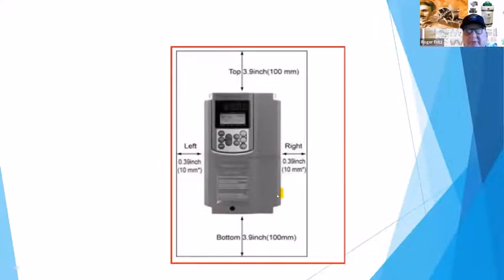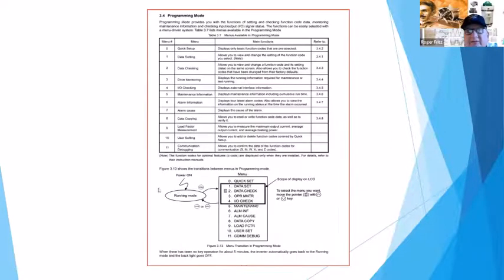The other main factor inside of a drive is cooling, because we are firing the transistors, and there are some losses in those, and so we do create some heat. One thing I found in the life of a VFD is to make sure that you follow the tolerances of distance away from another drive, and what the cooling area of that component is, what is recommended to stay at a certain temperature. They don't like a lot of high heat.